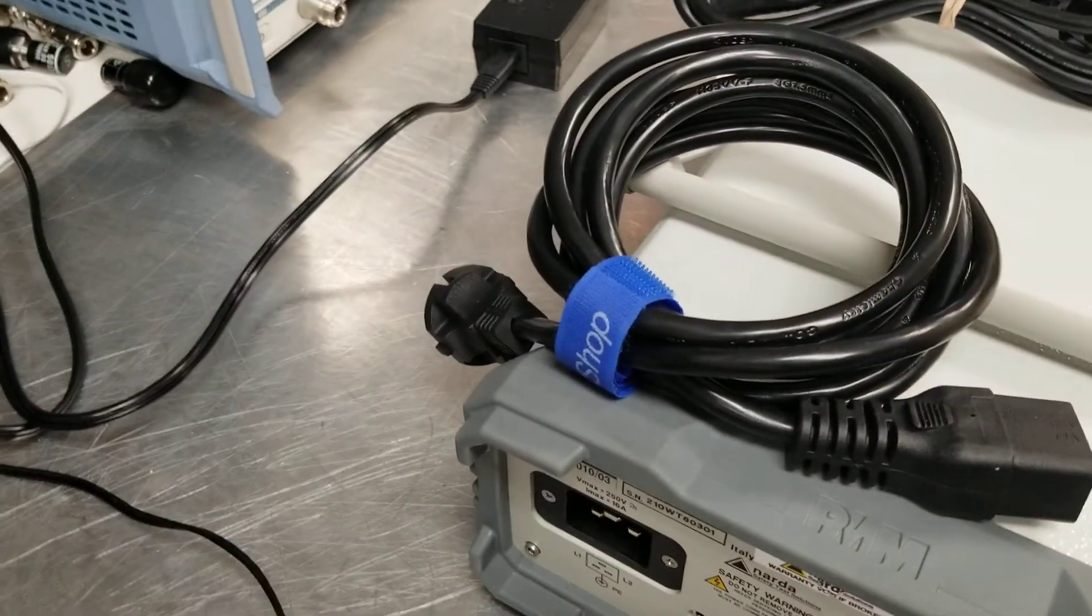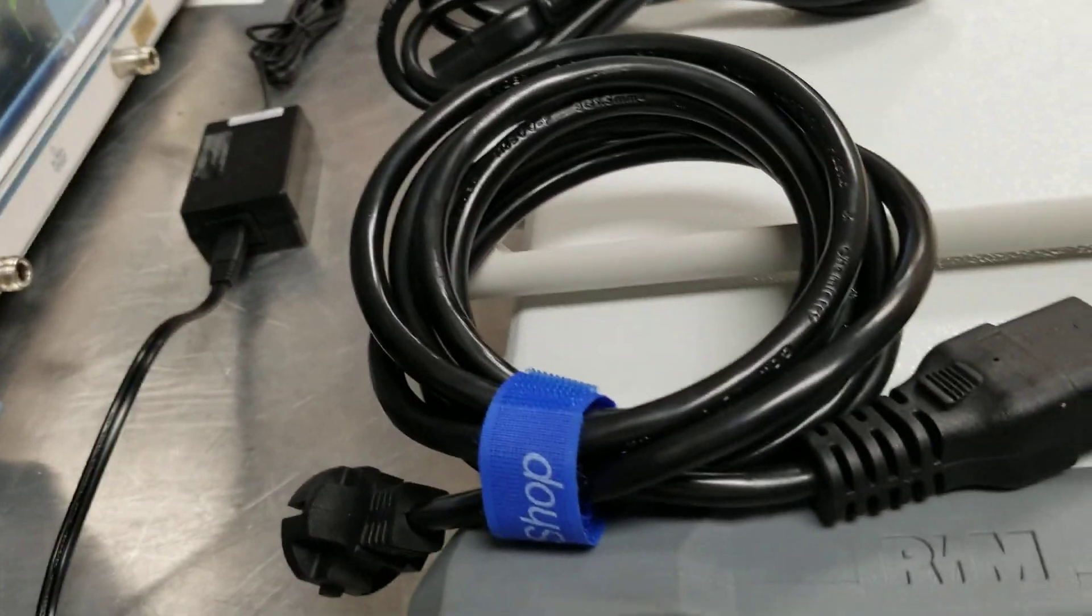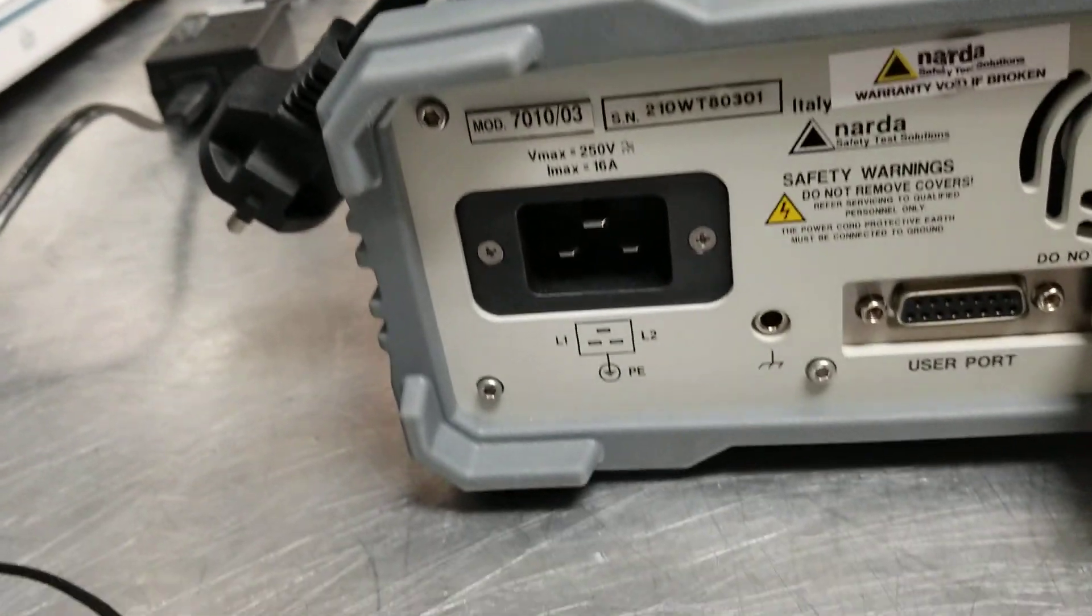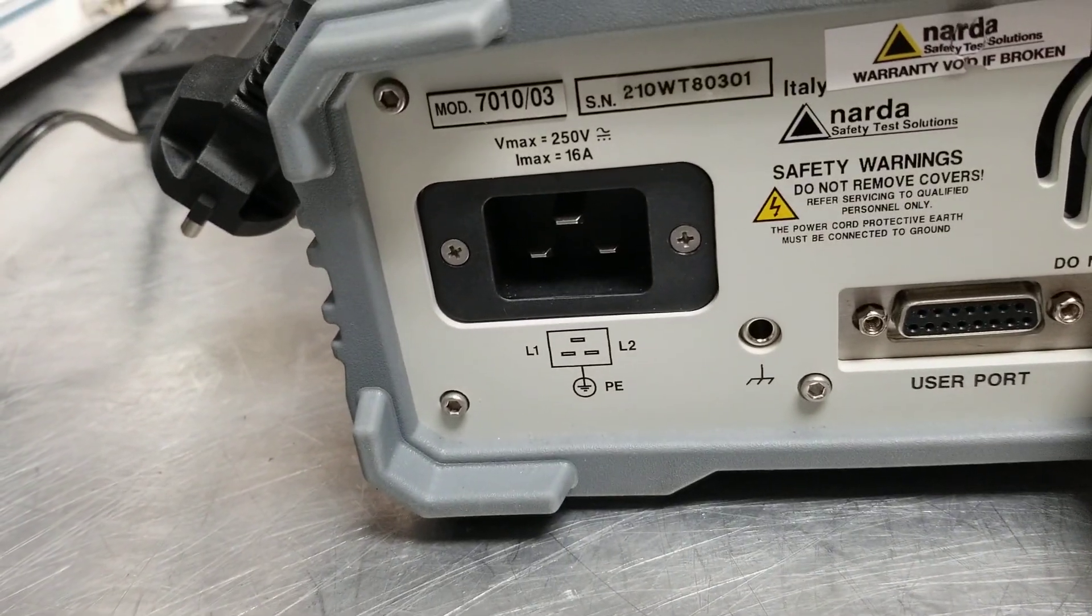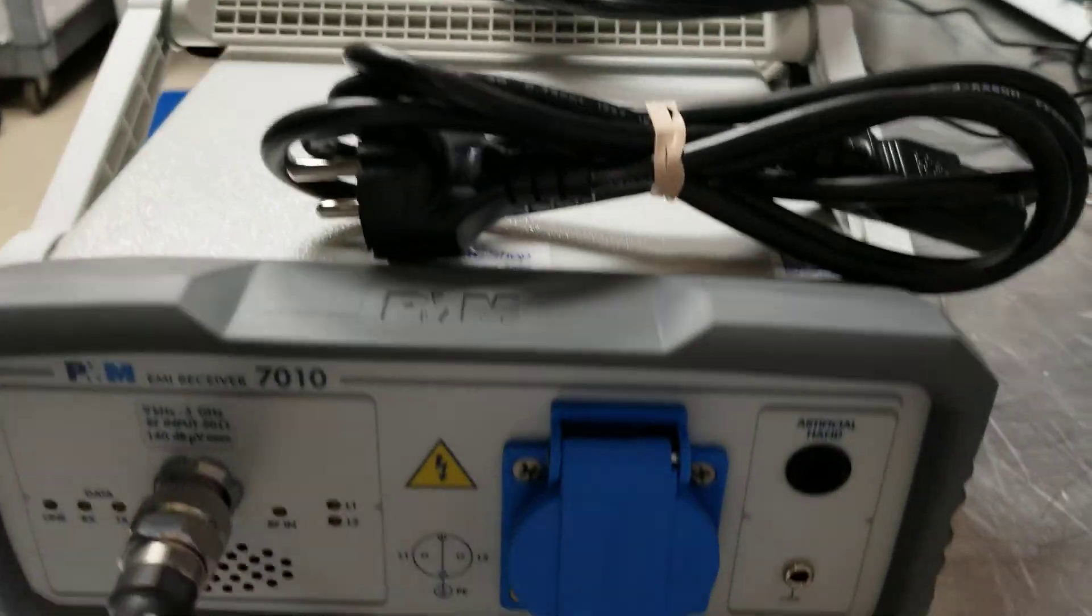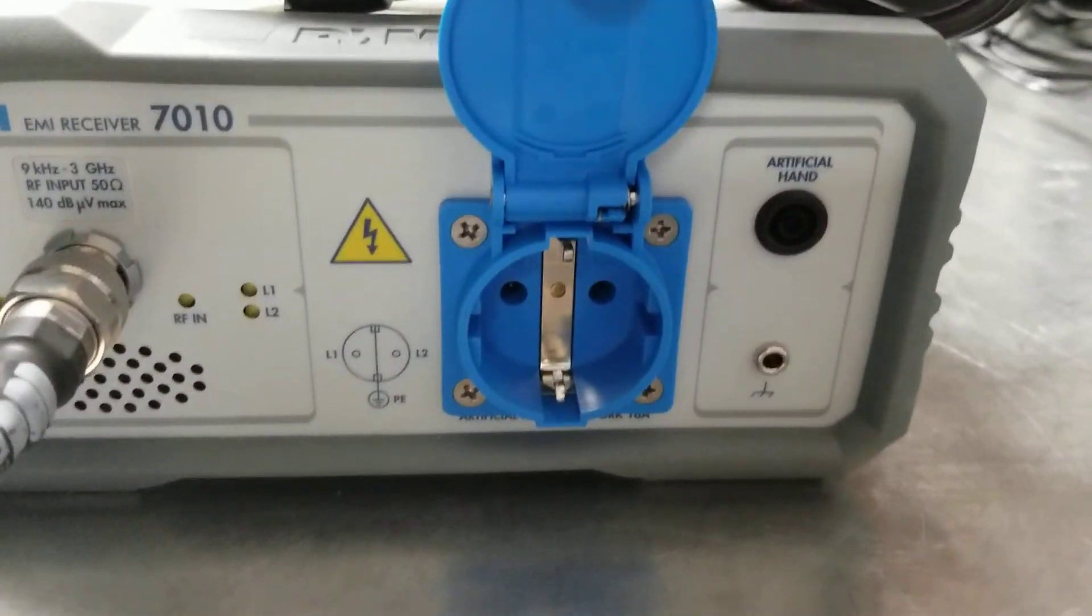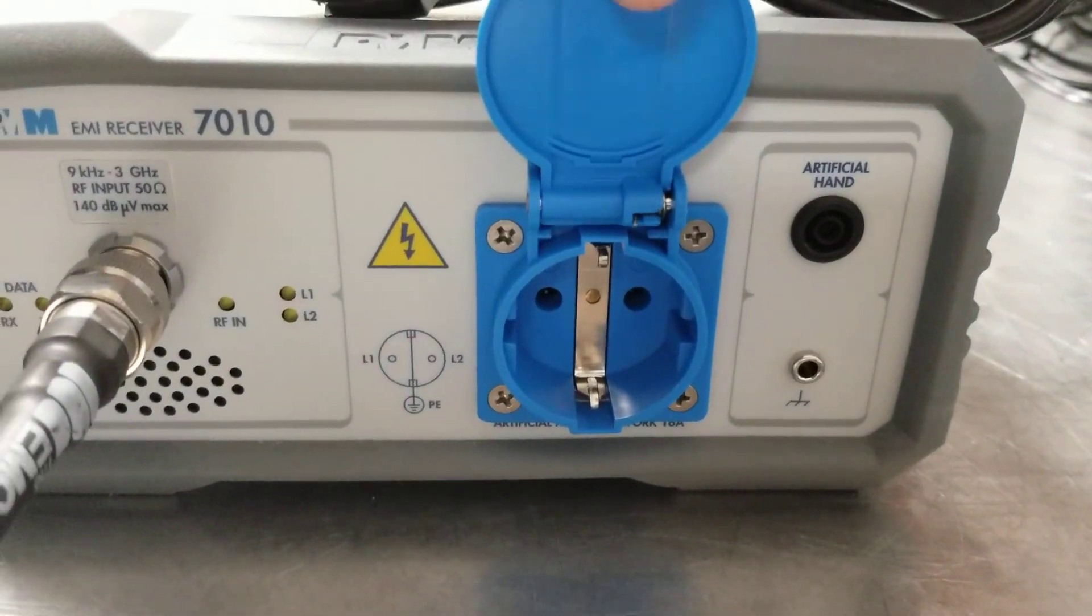Now if you're going to be using the LISN that is inside this unit, you would connect this cable up to the power receptacle here for your LISN, and then you would use this cable connected into here to supply power to your DUT.